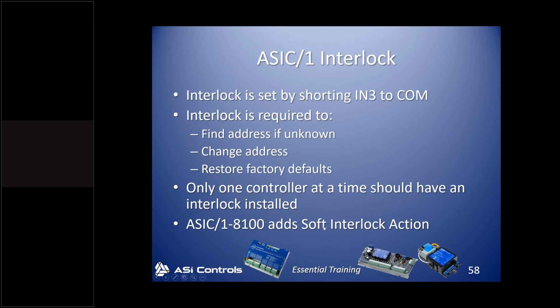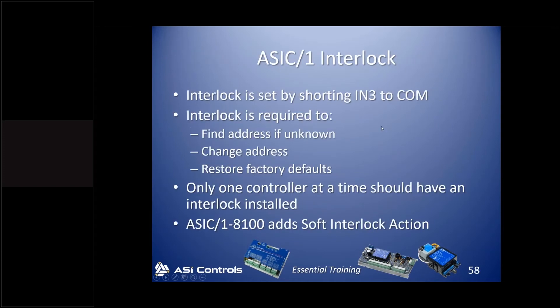The 8100 controller has a special soft interlock action that lets you, without physical access, temporarily set the interlock for 30 seconds so you can change the address. One customer with many 8100 controllers in remote locations needed to change addresses remotely, so we added that feature to the 8100. We've never added it to the 6100 — no one's ever really asked. For initial programming of ASIC/1s, I usually connect with a MicroSync.